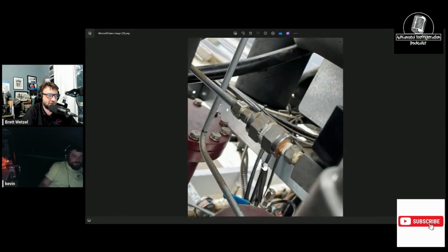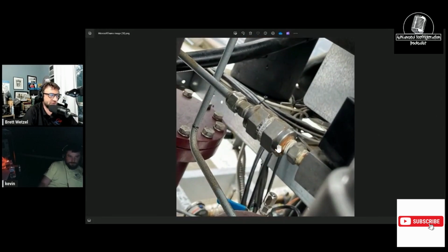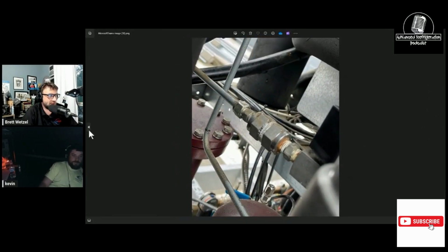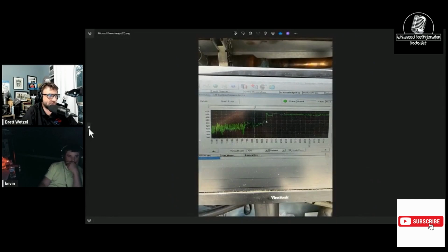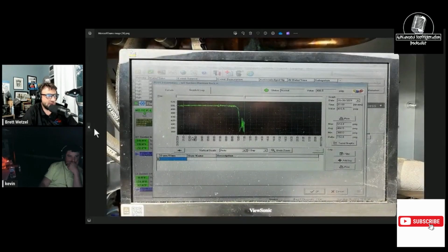All right. So that's the little itty bitty tiny filter that I've never seen one this teeny tiny. And this was for the hot gas injection. So he was having a problem where the rack at a certain point of time, around 6 o'clock, would fail. It would run fine, and then it would just not run fine after a little bit. And so what we found out is the hot gas solenoid, even though it was feeding.